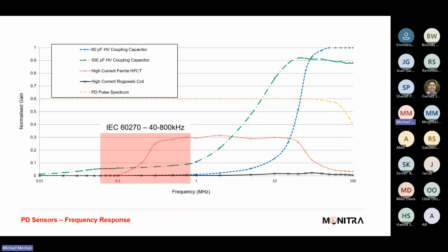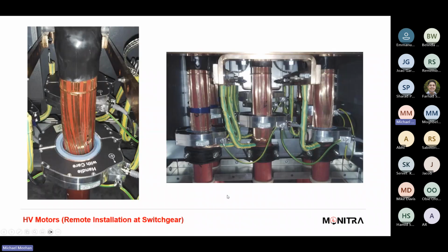You will just see a significant drop off at that range. It's PD activity, just because you're looking deeper into the winding, you won't see anything as close to your measurement point, but it can be useful to be able to check at those frequency ranges just to help with any PD analysis and cross PD checks.